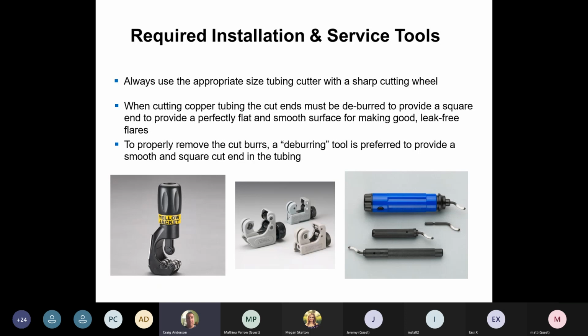Make sure when you're deburring the copper that you're pointing the copper down and the metal flakes are not going back into the tubing. I've seen it, guy standing there doing a deburring tool and all the filings are going back into the copper. So once those filings are in the copper and you start that unit, it starts flowing, especially when we get into mini splits. We have strainers and everything that are in the system. The copper is so small, it doesn't take much to block a 1/4-inch copper tube. So just be mindful when you're deburring it, you're deburring it good.